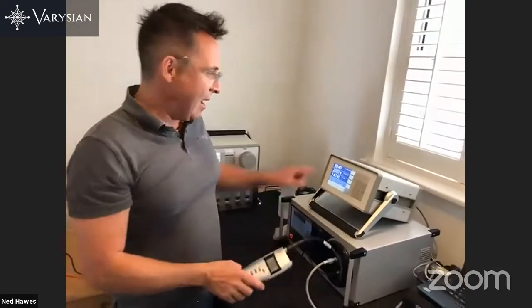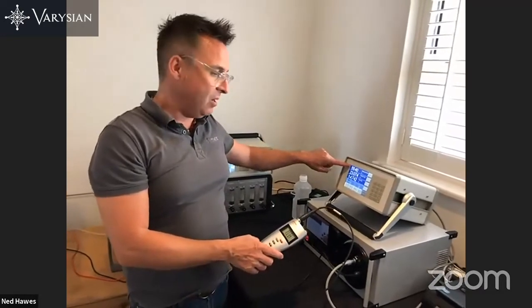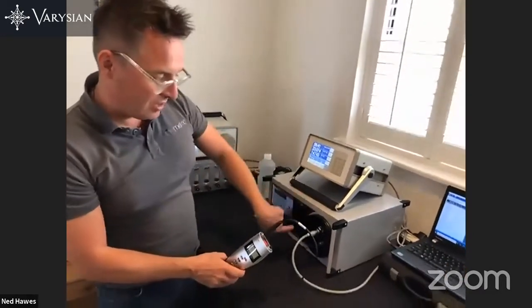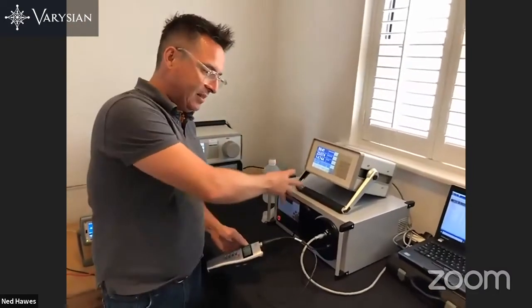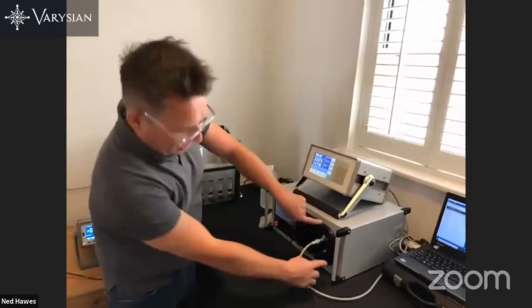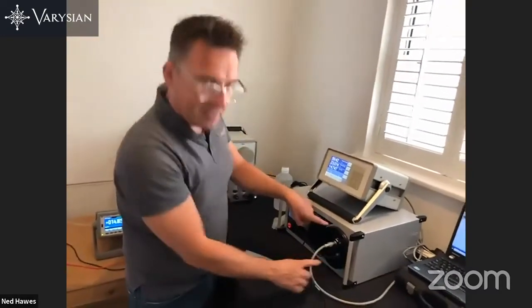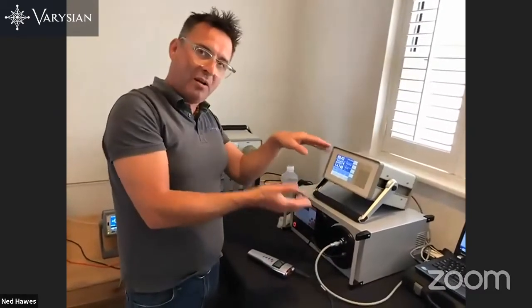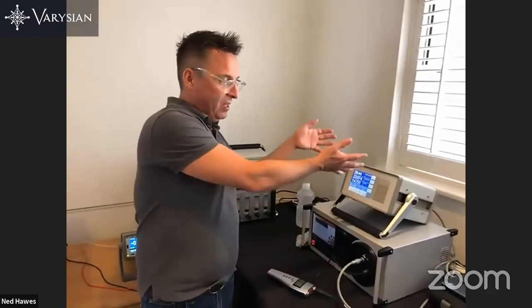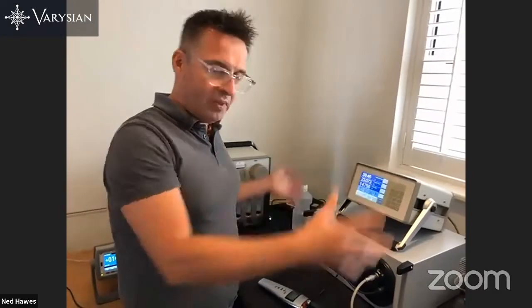Now, within that system, there's a degree of uncertainty. How good is that number? How accurate is that number? How good is this number? What's the condition in the chamber? Is it a uniform chamber? The fact is that these two probes are about 5 centimeters apart. Is the difference in the condition consistent over 5 centimeters? All of these combine to create uncertainty. What you will find is that with a chilled mirror as an external reference, your uncertainties of calibration are considerably lower than if you were just to use a standard RH point. That's the key thing. It's about creating a low uncertainty of calibration within such an environment.